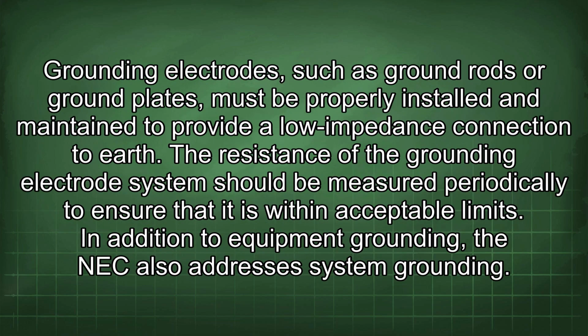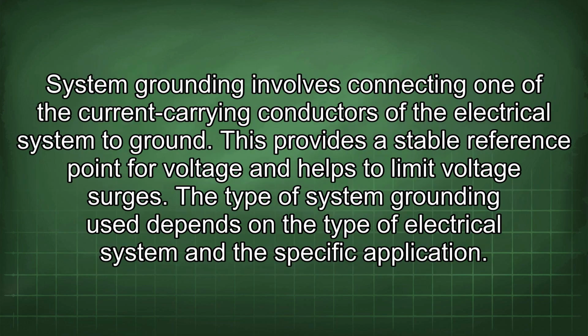Grounding electrodes, such as ground rods or ground plates, must be properly installed and maintained to provide a low impedance connection to earth. The resistance of the grounding electrode system should be measured periodically to ensure that it is within acceptable limits. In addition to equipment grounding, the NEC also addresses system grounding. System grounding involves connecting one of the current carrying conductors of the electrical system to ground. This provides a stable reference point for voltage and helps to limit voltage surges.